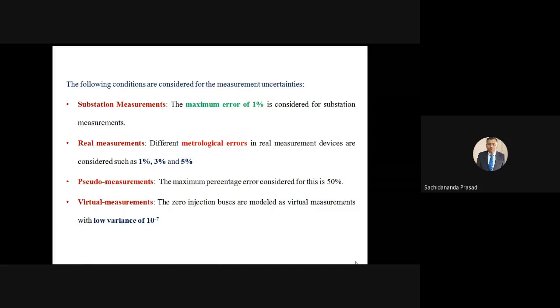For each measurement you have to define the noise associated with it, the maximum percentage of noise. For substation measurement, practically 1% maximum error is associated. For real measurement you can go up to 3%, 5%, not more than that is allowed. Pseudo measurements can go up to 50%, which you can see is the worst kind of measurement. Virtual measurements are very accurate, with very low errors.